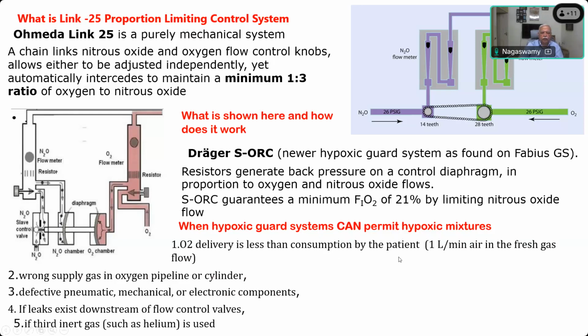So you require oxygen delivery more than what is required, 250 ml per minute. It's the minimum required oxygen amount. If you give less than the metabolic requirement, the patient can still receive hypoxia, from wrong supply, defective parts, leak, or the gas used.